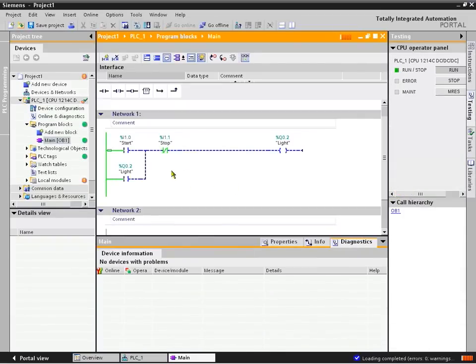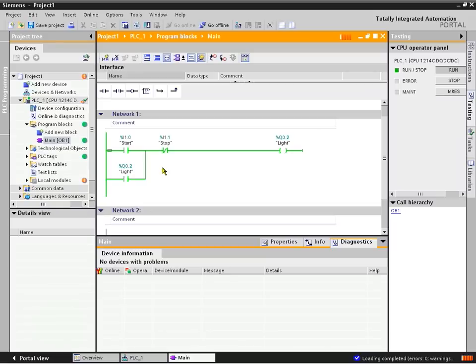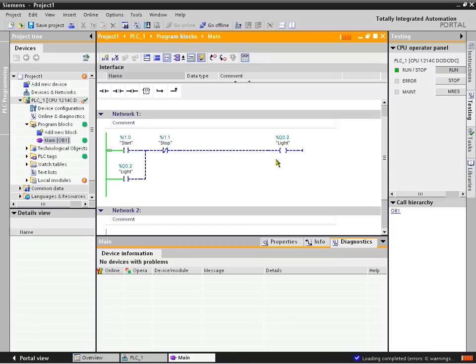And as that comes up, we can see that our conditions are open. When I turn on my start switch, it seals in that circuit. And I can remove my start switch as if it was a push button. It still has my output light active. And then I can break the connection with the normally closed stop button or push button. And then my circuit is complete, fully tested, and available for running.